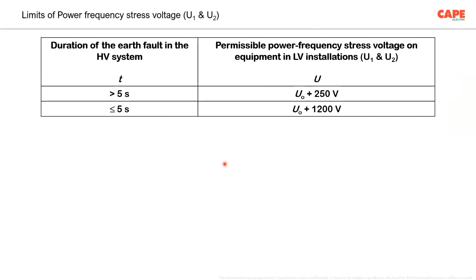Similarly, the second point is power frequency stress voltage. Stress voltage in the sense, due to some reason at the high voltage side or at the low voltage side, a temporary over voltage is happening in your electrical installation. Number one, your electrical appliance, including the wiring, including the installation equipment, must be able to withstand a certain minimum limit. And that particular limit is shown in this particular picture. U1 and U2 mean the stress voltage on the transformer or in your installation.